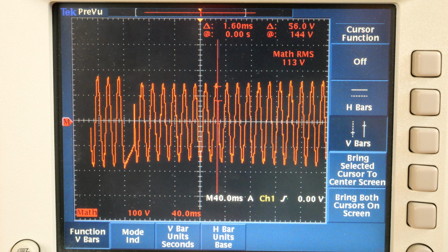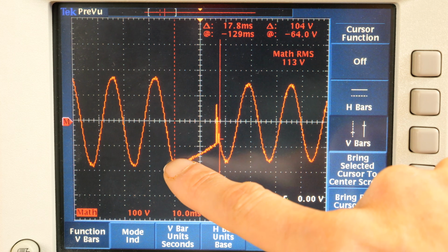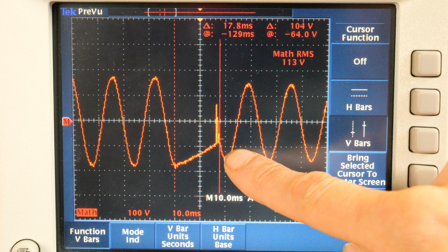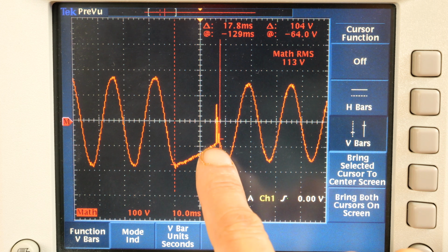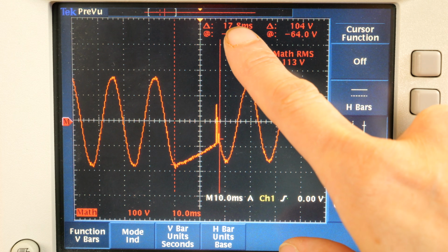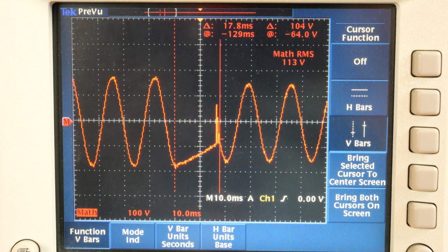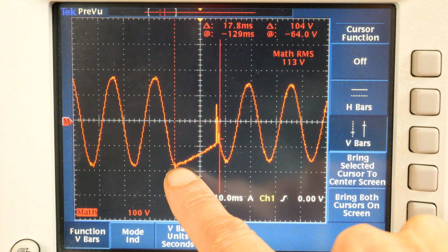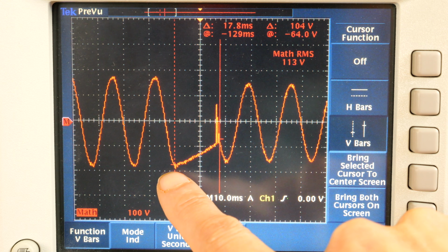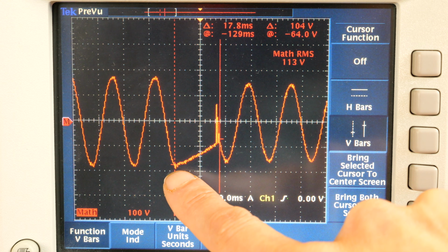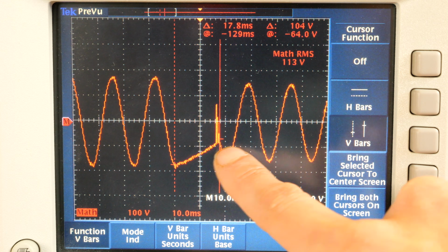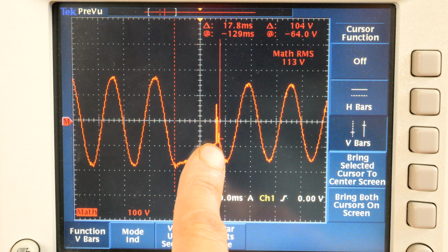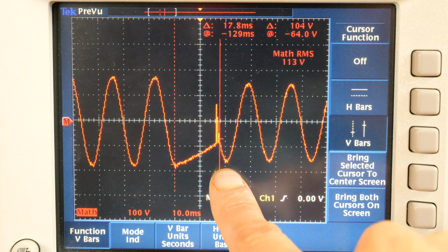We can zoom into that. So it's not a perfect switchover where you're not gonna see any kind of artifacts. But from this point to this point, it's only a delta of 17.8 milliseconds. During this time, the voltage is still fairly low. It's being discharged, so technically anything connected to this is still being powered. At this point, the UPS inverter kicks in, drawing power from the battery, and it continues a negative cycle and then back up.